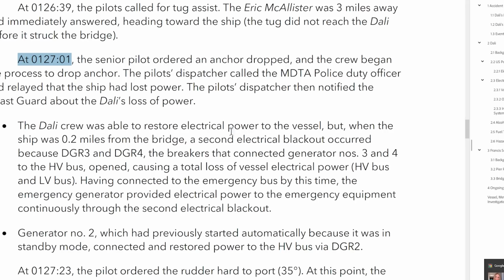They were able to restore electrical power to the vessel, but when the ship was 0.2 miles from the bridge, a second electrical blackout occurred because the breakers connecting diesel generators 3 and 4 to the high voltage bus opened, causing a total loss of electrical power.